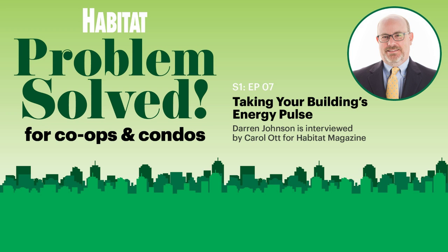That allows an energy engineer to analyze that big data and to have a better, more thorough understanding of the performance of the building. And it allows you to create a benchmark to say, okay, this is where we are. So let's create some parameters around that performance benchmark. That way we can see if there are variations that take place so that you're going to be able to see before equipment starts to fail. And so it allows it to be almost predictive in the sense that you can see things that are happening. And so if there is a service disruption, it's going to be either eliminated if you catch it early enough, or it's going to be minimized so that it's not after the fact when something just fails completely.